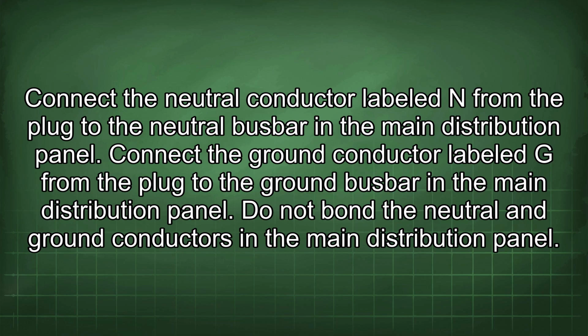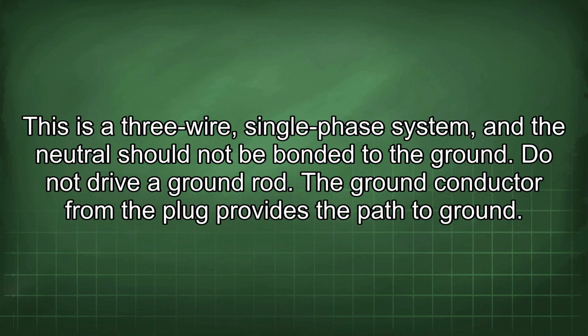Connect the ground conductor labeled G from the plug to the ground busbar in the main distribution panel. Do not bond the neutral and ground conductors in the main distribution panel. This is a 3-wire, single-phase system, and the neutral should not be bonded to the ground. Do not drive a ground rod. The ground conductor from the plug provides the path to ground.